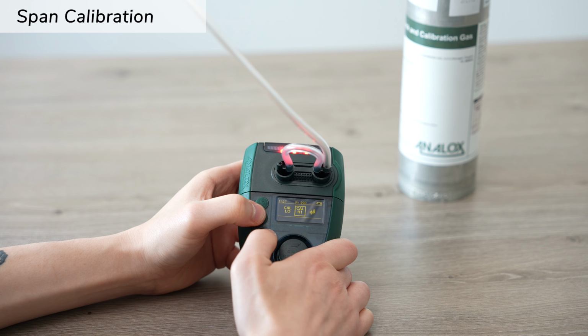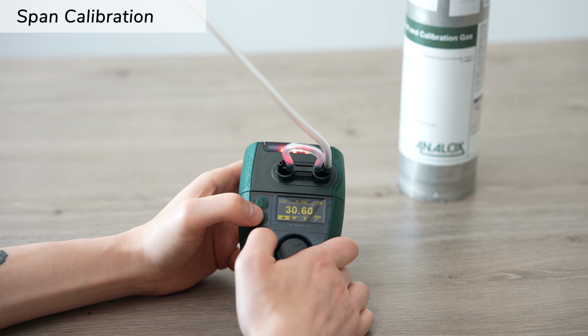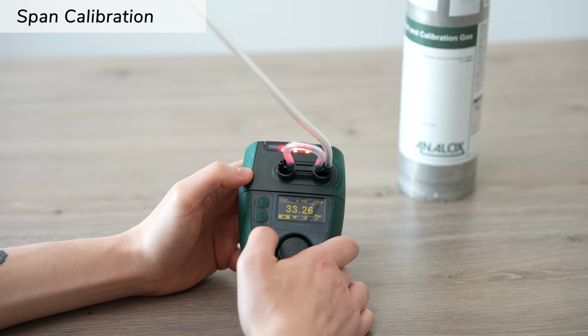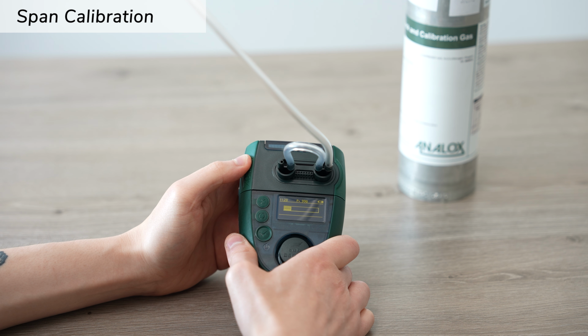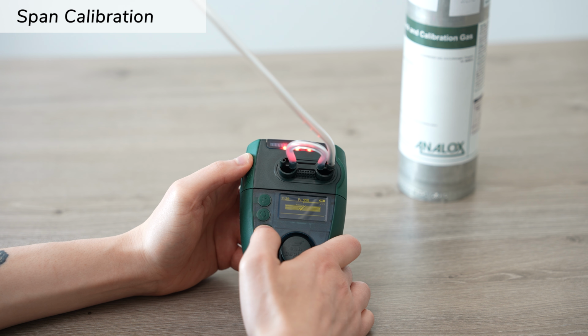From here, we can use the arrow keys to adjust the span gas value. On the Sub Aspida, this is measured in millibar, with 30 millibar being equal to 3%. Let's adjust this to 50 millibar for our 5% calibration gas. Now we can start the calibration. Once completed, close the regulator and allow the sensor to warm up.